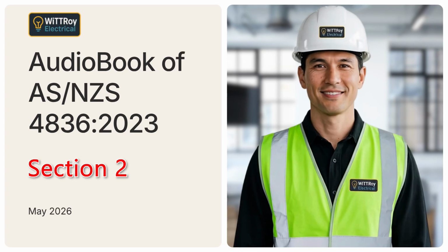Clause 2.7. Means of reducing risk. Clause 2.7 explains practical ways to reduce electrical risk. Electrical safety should be maximized wherever possible when working with electrical installations or equipment. Electrical safety depends on good job planning by a competent person. It also depends on correct isolation and testing procedures, suitable safety equipment and tools, suitable test instruments, suitable PPE, competent workers, warning notices, and barriers that prevent accidental contact with energized parts.